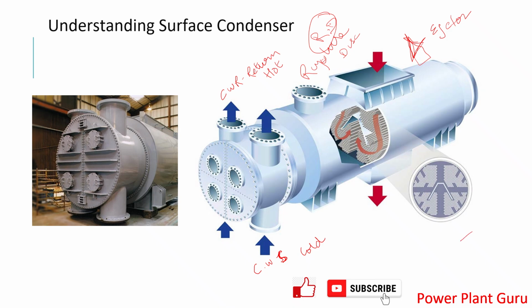Maybe rupture disk is nothing but a kind of disk or a kind of plate which is designed to burst if you apply pressure from any one side. It will be designed like this, okay, there will be certain marks. So let's say the pressure setting would be 1.5 kg per centimeter square or 2 kg per centimeter square. If you apply pressure more than that, it will give way. Okay, and then it will be open to atmosphere. So beyond that, your pressure will not rise.